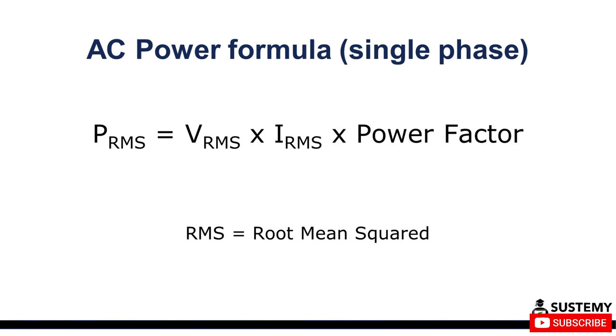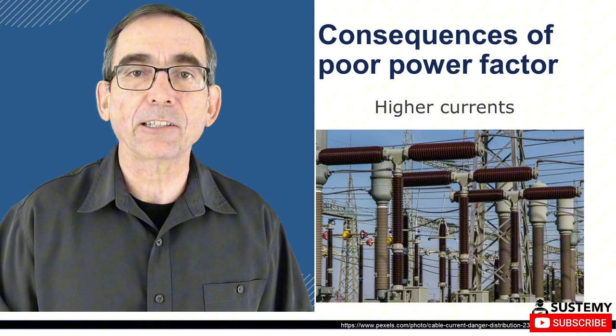For an AC circuit, the root mean squared power measured over one cycle is the RMS voltage times the RMS current times the power factor, RMS being the root mean square. Where the electrical loads at a site are such that the site has a poor power factor, electrical currents increase above what they would be were the power factor to be 1 or close to 1. This both increases loading on switchboards, and it also means that the current your electricity grid needs to supply is higher than it would be otherwise.